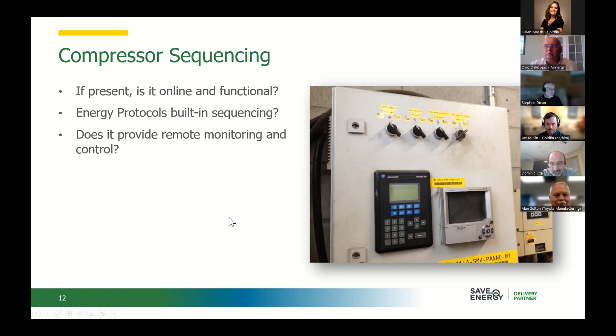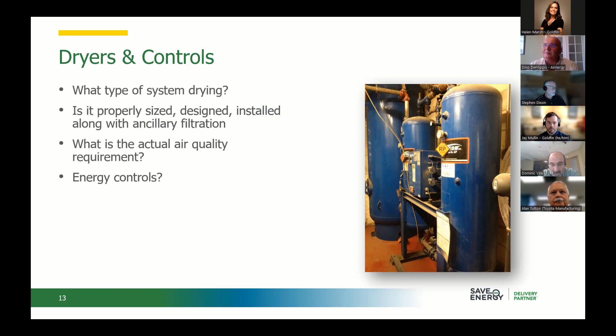That's correct. The first thing when I see any type of drying system in a plant, I'll always ask the customer what are the requirements for compressed air quality at the point of use. Whether you're stamping, pharmaceutical, or food, there must be some sort of SOP or compressed air quality document that we need to look at. Most of the time they're over-designed or under-designed, or if they're just a heatless type desiccant dryer with no purge economizer or dew point energy mode, we're blowing 15% of that compressed air out the exhaust muffler. So it's good to look at what the requirements are at the point of use on the demand side to properly know what sort of drying you need.